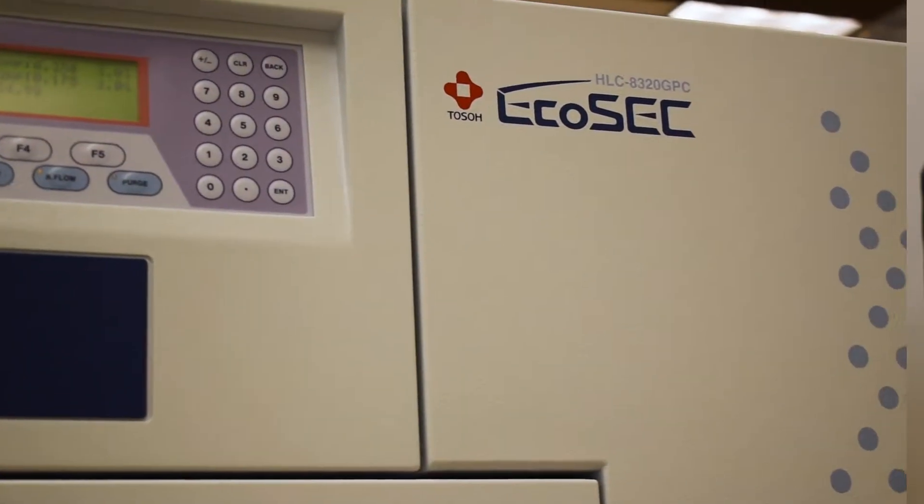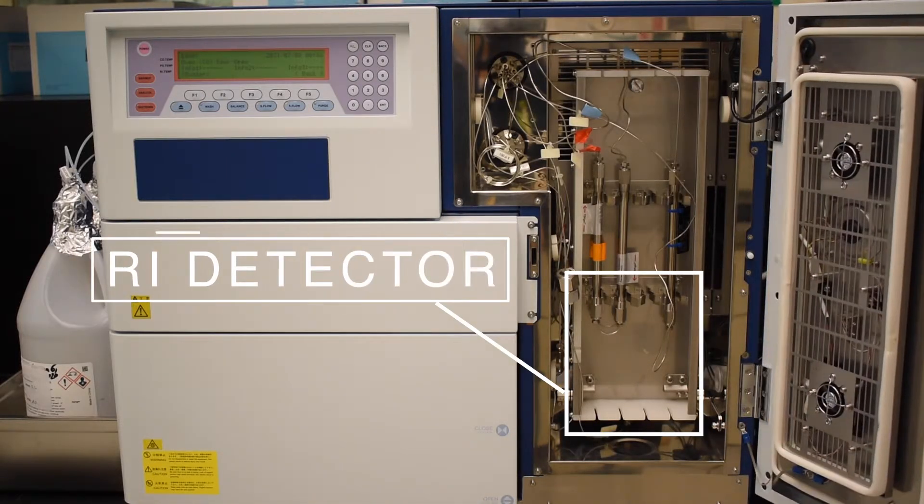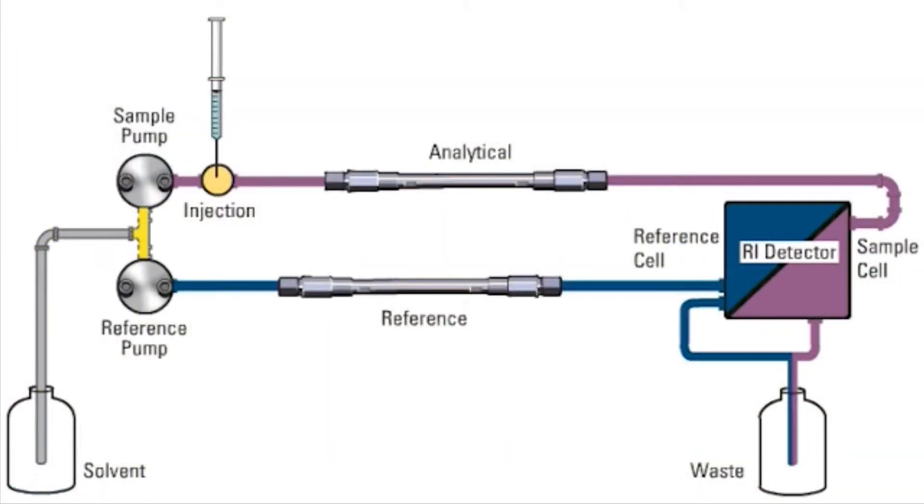Tosoh's GPC systems, the EcoSec and the EcoSec Elite, are unique from other GPC systems in three main ways. The first way is that it implements a dual-flow RI detector. In all other GPC systems, the RI detector has a reference cell that is stationary. The stationary reference cell contains eluent that degrades over time, ensuring substantial baseline drift. In the EcoSec and EcoSec Elite, because of the dual-flow RI detector, an extra pump is purging fresh solvent, ensuring that there is no baseline drift over time.